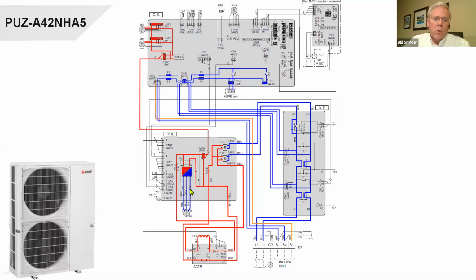You see a couple little coils here and here. We're monitoring that voltage up here on this board. That's coming through these signals here. Some of these other signals coming in here are monitoring the voltages and seeing what we're telling the compressor to do, what it's actually doing, and what type of signal it's getting. If it sees something it really doesn't like, then it's going to shut the equipment down or give you an error code or both.